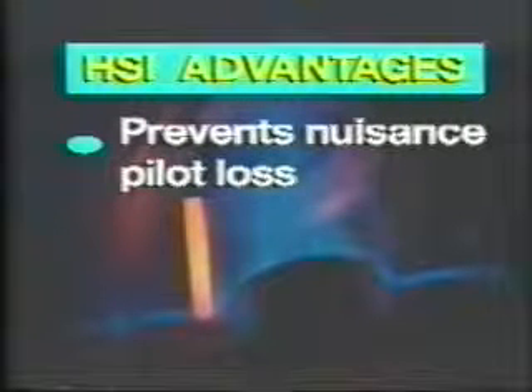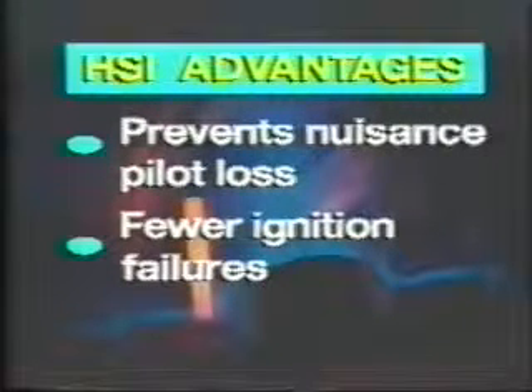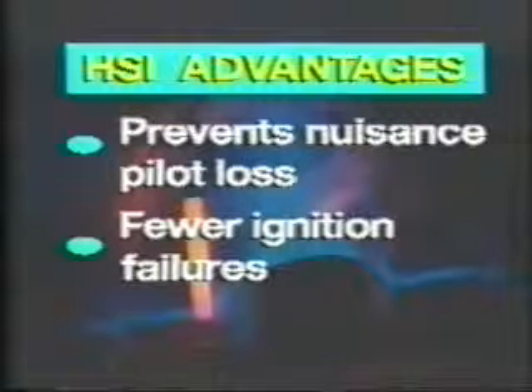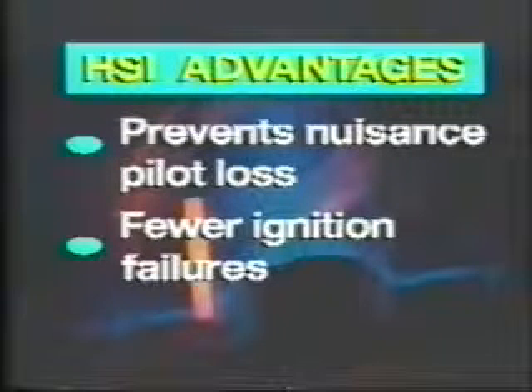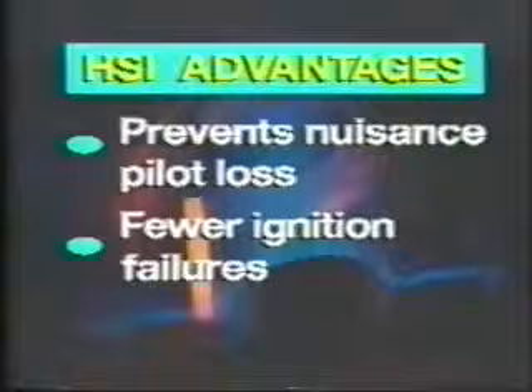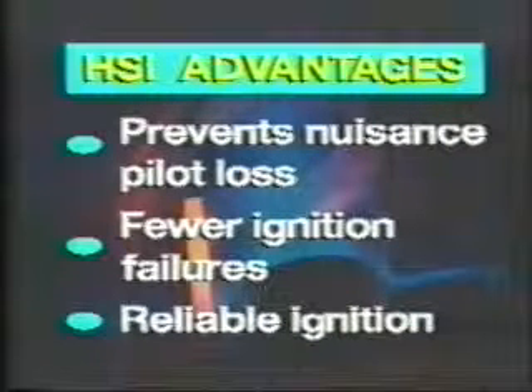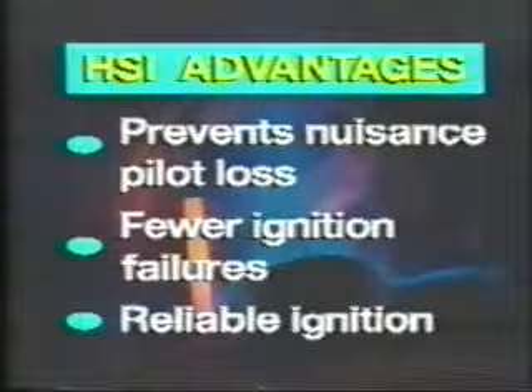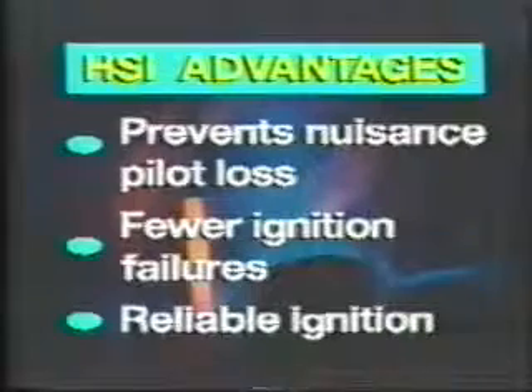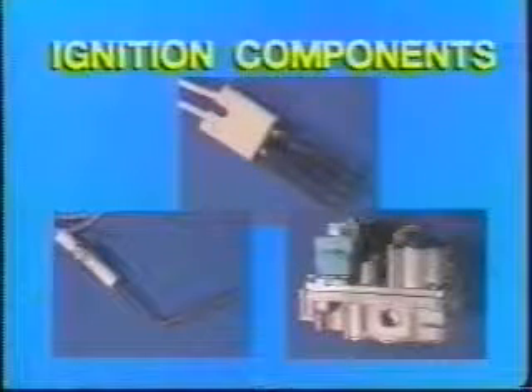Hot surface ignition solves 2 problems common with standing pilots: nuisance loss of pilot flame and failure to ignite on call for heat. The igniter generates more than twice the energy of a standing pilot flame. This higher energy helps ensure reliable ignition under all burner conditions. The control system uses 3 components for the ignition sequence: an igniter, a flame sensor, and the gas valve.